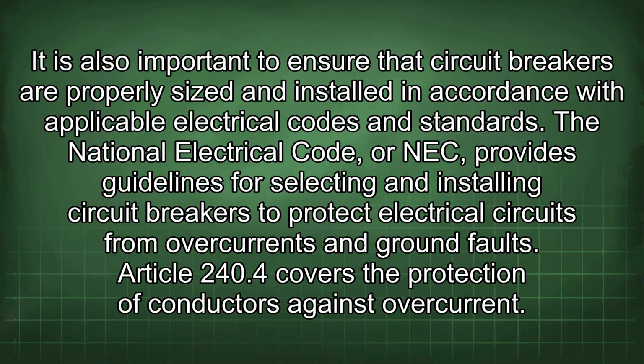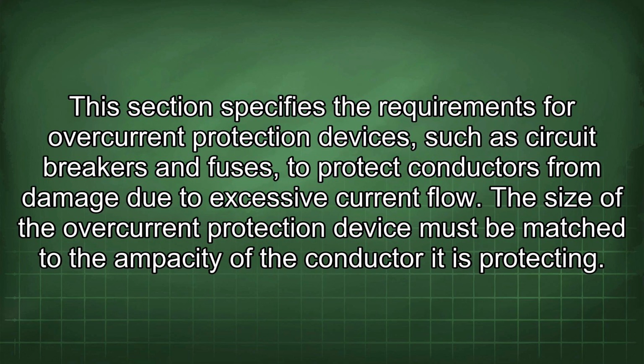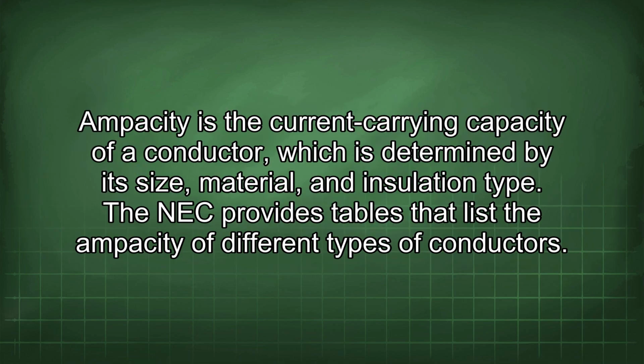It is also important to ensure that circuit breakers are properly sized and installed in accordance with applicable electrical codes and standards. The National Electrical Code, or NEC, provides guidelines for selecting and installing circuit breakers to protect electrical circuits from overcurrents and ground faults. Article 240.4 covers the protection of conductors against overcurrent. This section specifies the requirements for overcurrent protection devices, such as circuit breakers and fuses, to protect conductors from damage due to excessive current flow. The size of the overcurrent protection device must be matched to the ampacity of the conductor it is protecting. Ampacity is the current carrying capacity of a conductor, which is determined by its size, material, and insulation type.